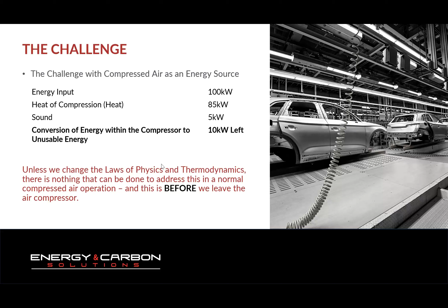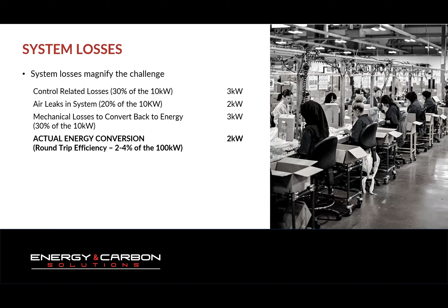Once we've actually got out of the air compressor, we may have something like, for example, a non-VSD machine. So we lose about 30% of that 10 kilowatts, so we lose another 3 kilowatts of energy. We have air leaks in the system. Let's say it's another 20%. And then we have mechanical losses. So the conversion of energy back to a piston or an air tool, we lose about another 30%. So we may put in 100 kilowatts of energy, but our round trip efficiency now is between 2 and 4% of that 100 kilowatts. Next slide, Jared.